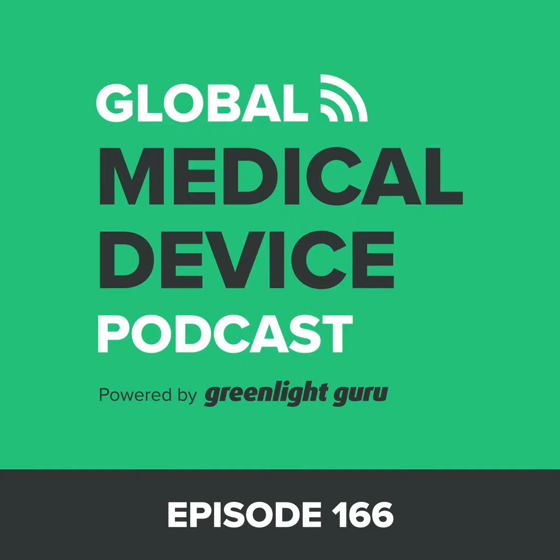Yep. Yeah. So sometimes suppliers would provide USP Class 6 information about the material, and that was kind of a head scratcher. I'm like, this isn't really what I need from a biocompatibility standpoint. Forget the fact that the raw material that I'm going to be purchasing, I'm probably going to process further, whether it's pellets for extrusion or injection molding or whatever the case may be. I'm going to do something else to that material that, arguably, could somehow change its physical characteristics in some way.